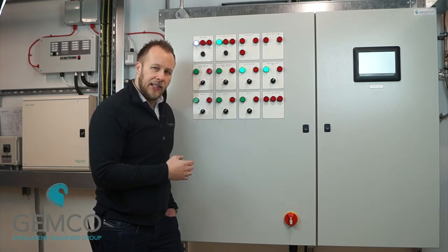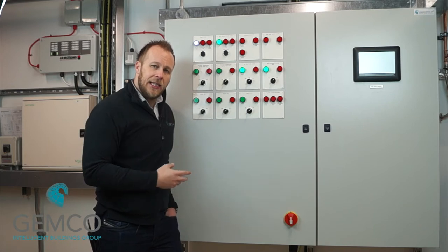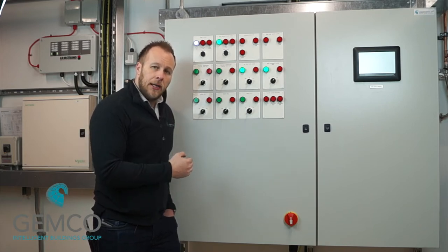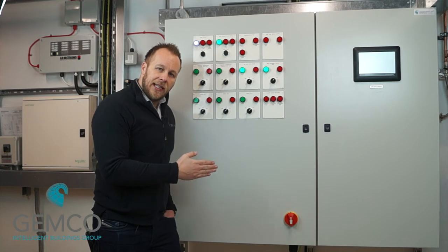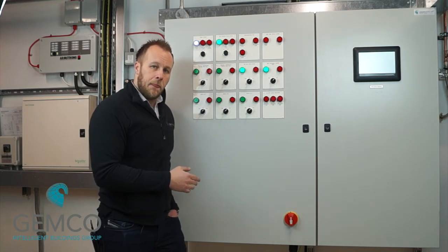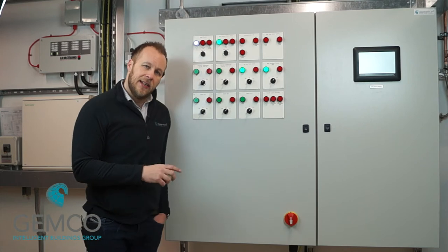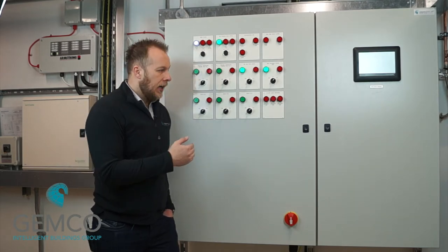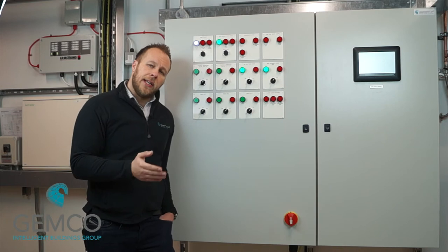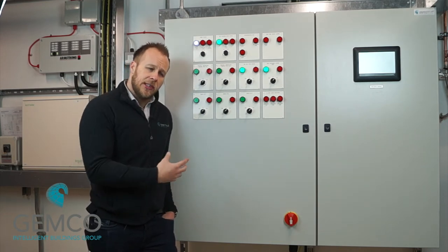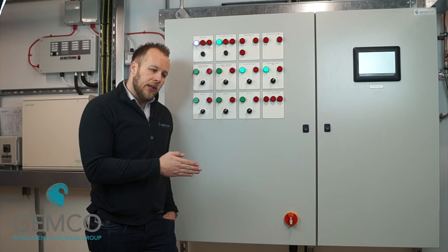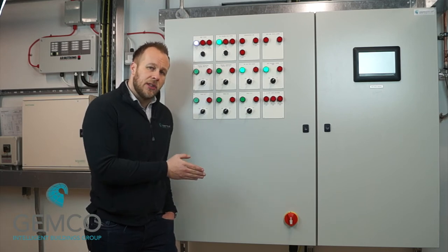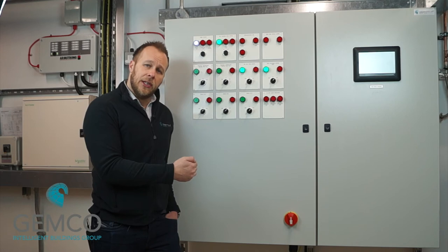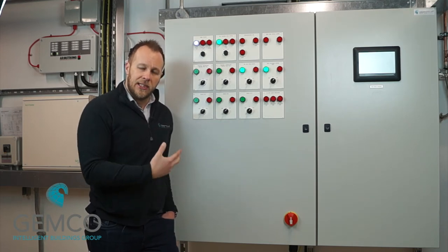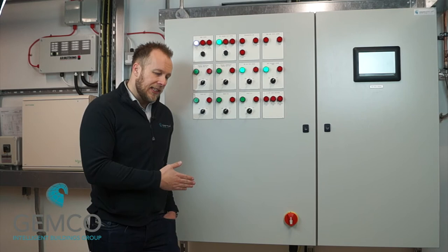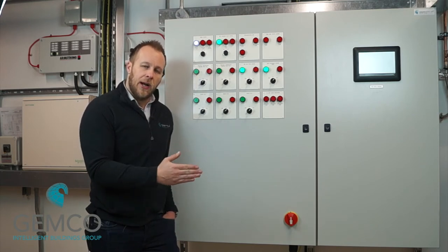Now, the optimization is a way of intelligently bringing on the plant with enough time to get to set point before the start of occupancy. So what that means is if you've got a time switch set 8 till 6, the system will look at the outside air temperature and the internal temperature and say, well, I need to come on a certain amount of time before the start of occupancy in order to be up to temperature for the start of occupancy. So it's an intelligent learning process that is continuously happening in the background throughout the year.